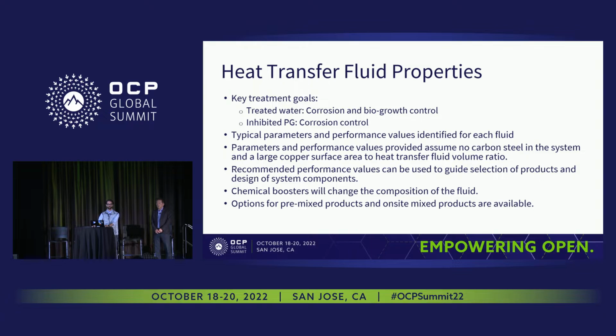The workstream at this point has assumed that no carbon steel will be in the system, and the systems will have a large copper surface area to water ratio due to the wetted surface area of the cold plates. The properties and parameters in these white papers can be used to aid in the selection of heat transfer fluids and additives.